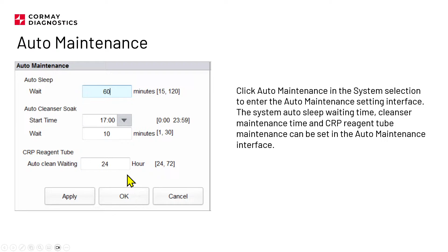Auto maintenance. Here are the settings for automatic processes, like auto sleep, auto cleanser soak, CRP reagent tube, auto clean waiting. It's information on how often the auto cleaning of the CRP tube will be done by the analyzer, even when the device is idle, let's say every 24 hours. Here you have the standard settings for that. You can modify them, of course.